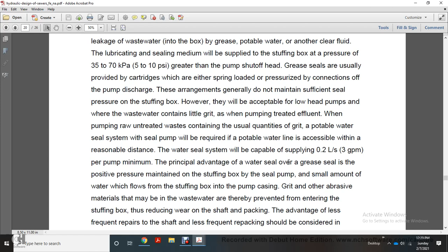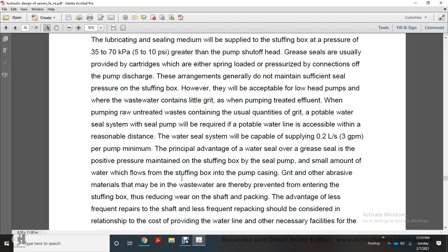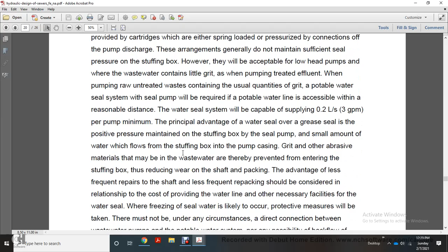The principal advantage of the water seal over the grease seal is the positive pressure maintained on the stuffing box by the seal pump. A small amount of the water flows through the stuffing box into the pump casing. Grit and other abrasive material in the wastewater are thereby prevented from entering the stuffing box, reducing wear on the shaft. The packing has the advantage of less frequent repairs of the shaft. Less frequent repacking should be considered in relation to cost, providing water line and other necessary facilities with the water seal.